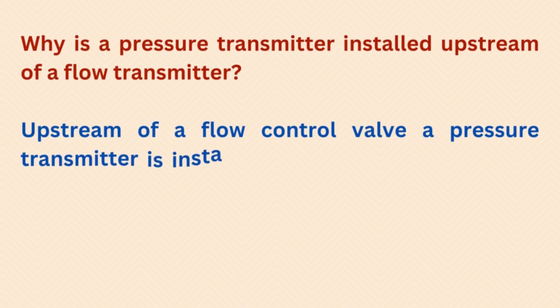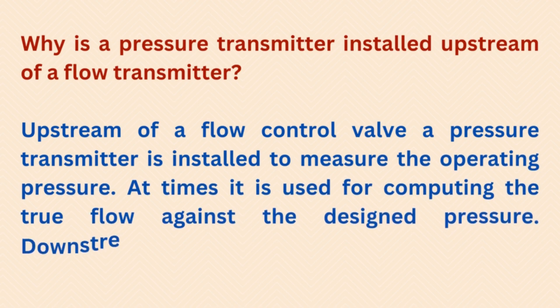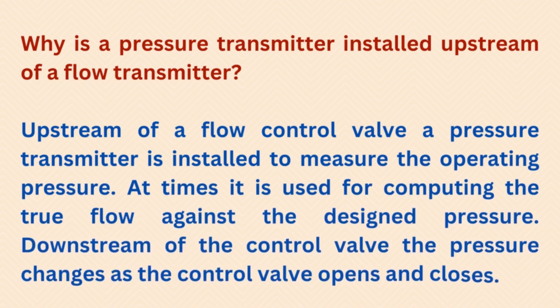Why is a pressure transmitter installed upstream of a flow transmitter, upstream of a flow control valve? A pressure transmitter is installed to measure the operating pressure; at times it is used for computing the true flow against the designed pressure. Downstream of the control valve, the pressure changes as the control valve opens and closes.